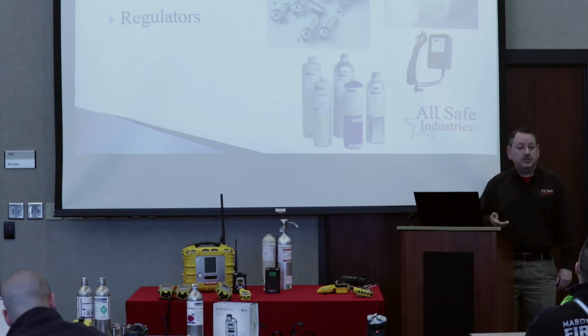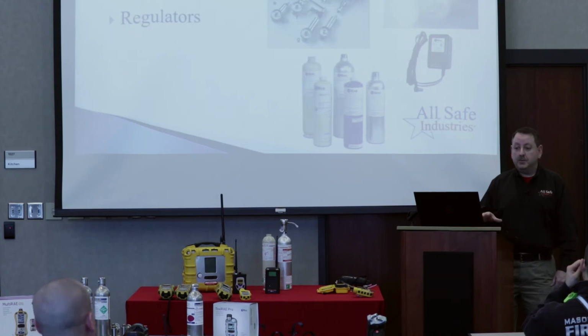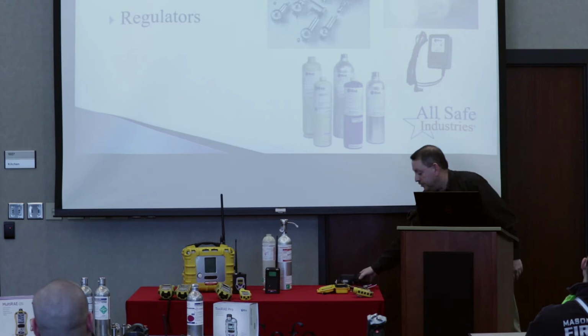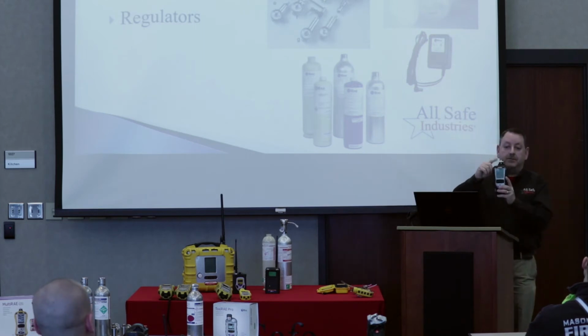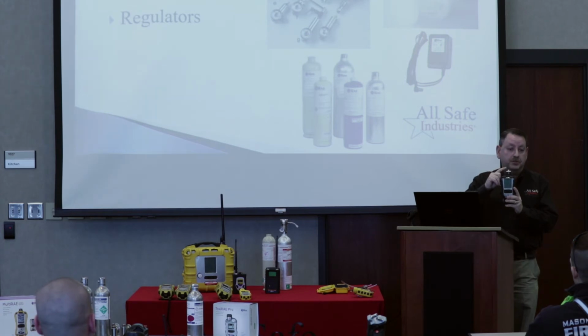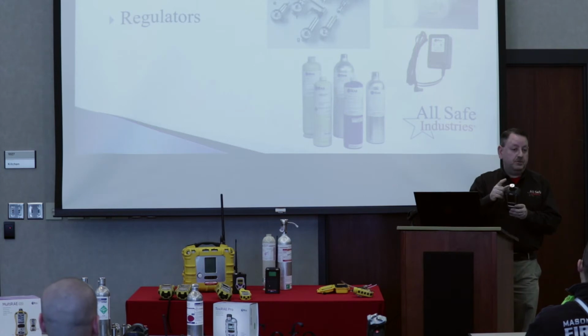Again, the tubing is just useful to draw samples to you, whether it's in a hazmat situation or a confined space situation. As I pointed out earlier, your pumped instruments will typically have a filter on the top, and so you want to always make sure that you're using this filter. I've rebuilt pumps thousands of times, and it's always better to use the filter. It keeps out the dust and the dirt, and it's even a hydrophobic filter, so we refer to it as a water trap filter.